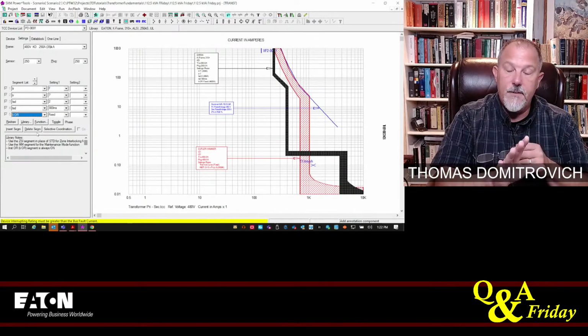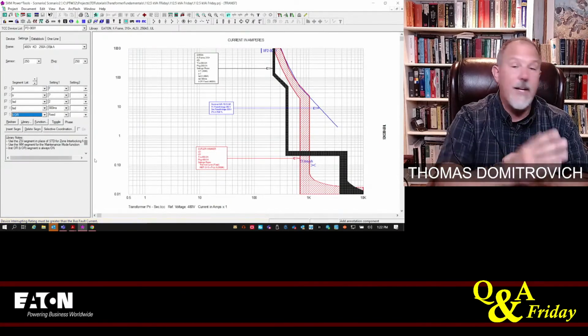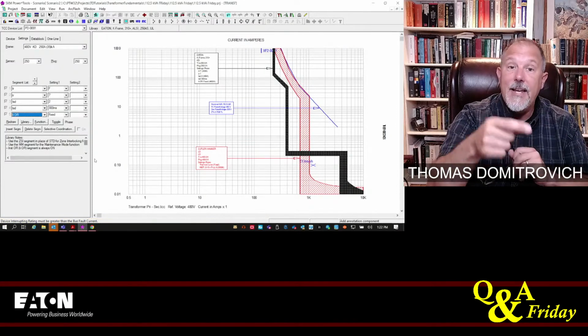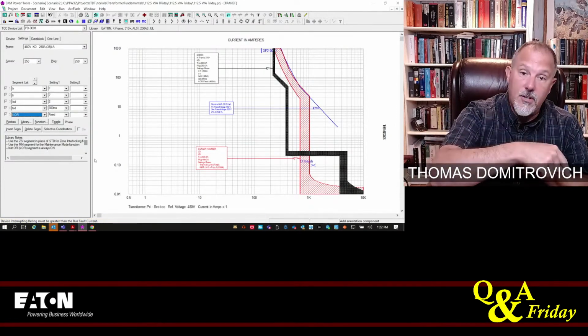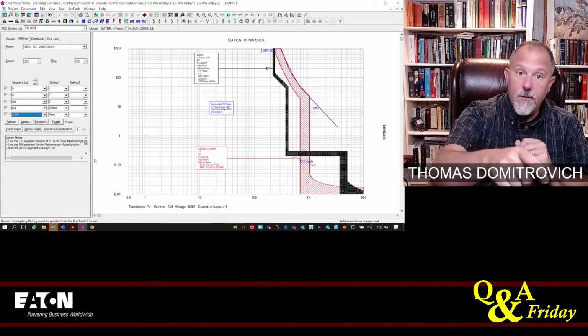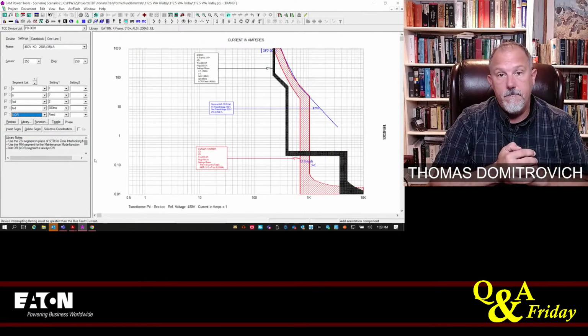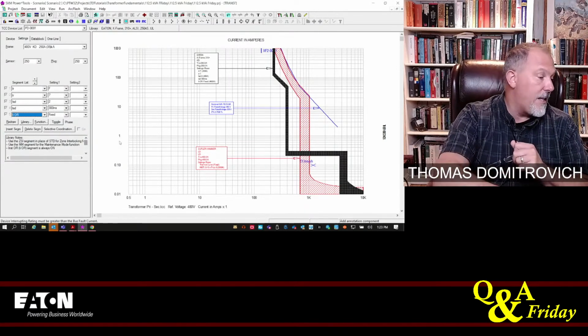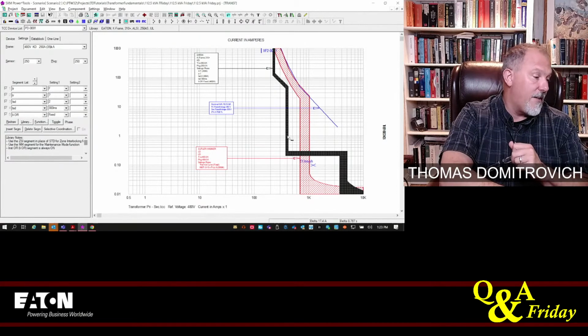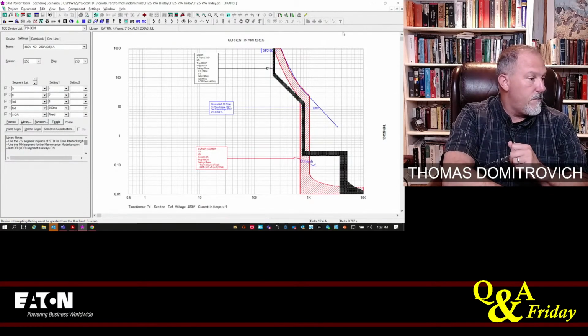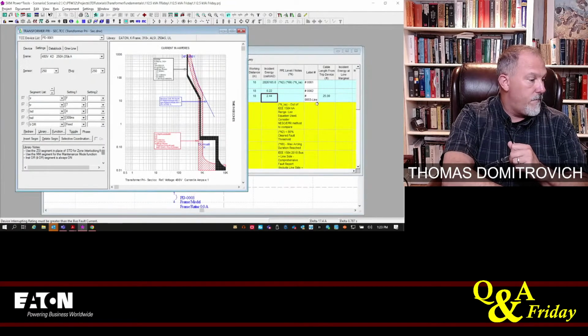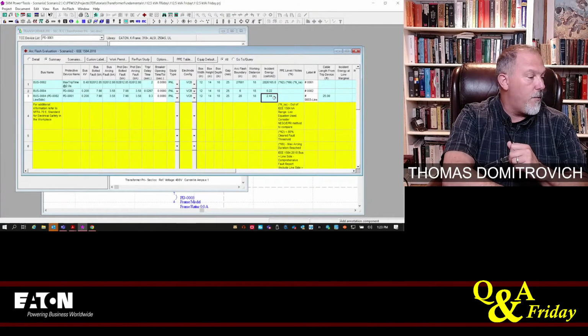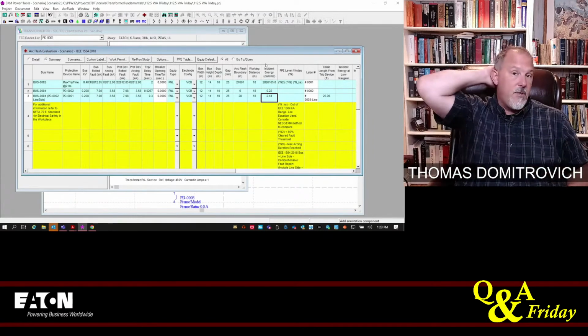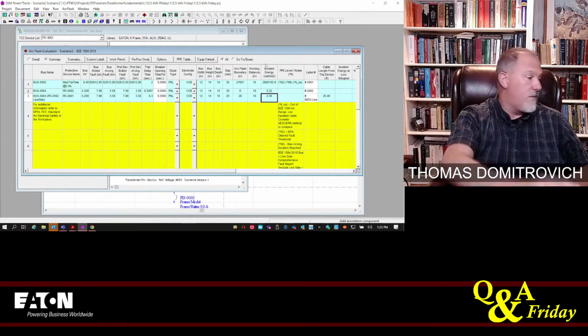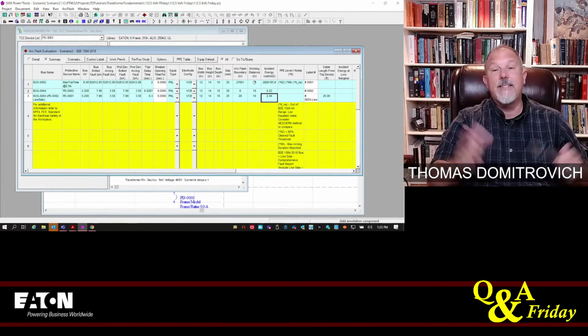That is what the arc reduction maintenance switch will do for you. That's what the electronic trip unit does, and it provides better short circuit protection and overload protection for that transformer. Your electronic trip units can help you significantly. And if you have to move that up, you can. And you're at 2.44 calories without the maintenance mode. You put it in maintenance mode and you are less than a calorie.